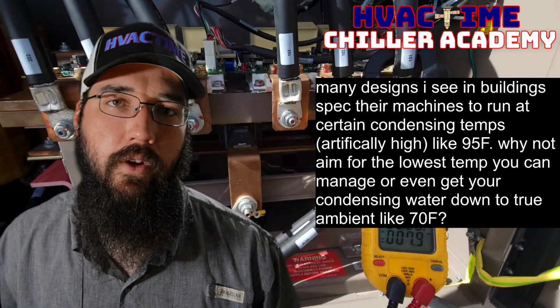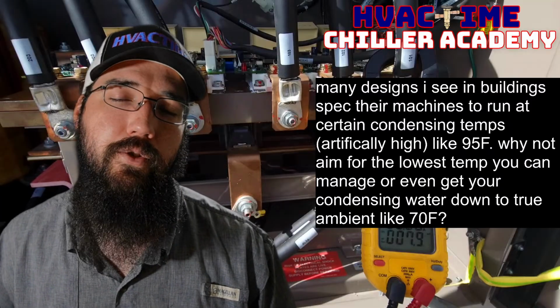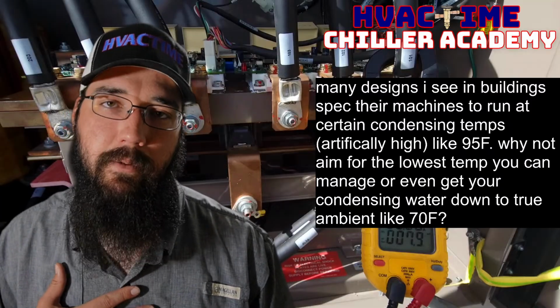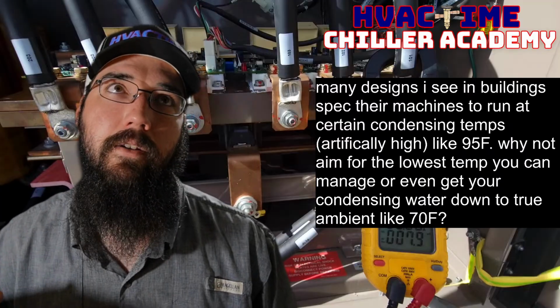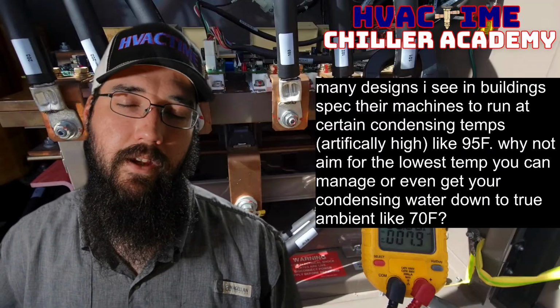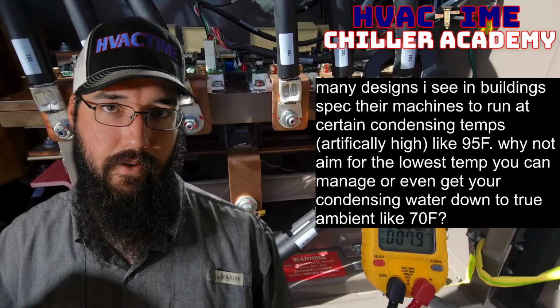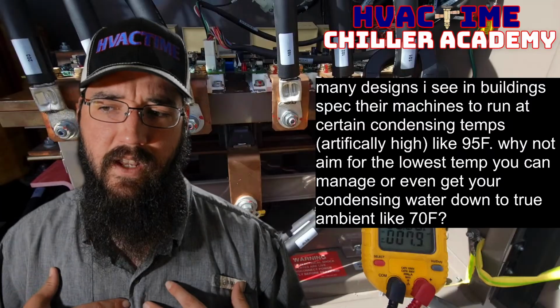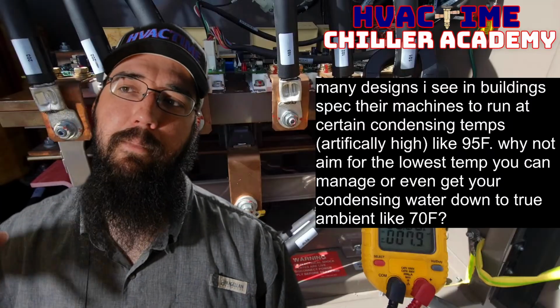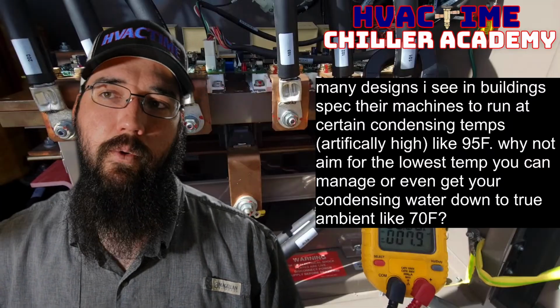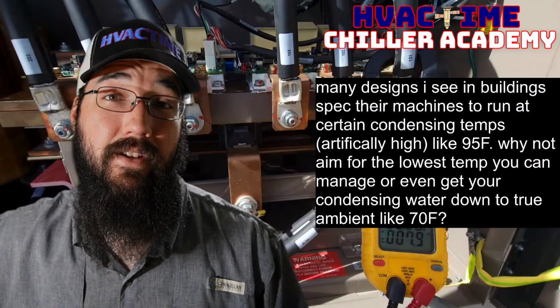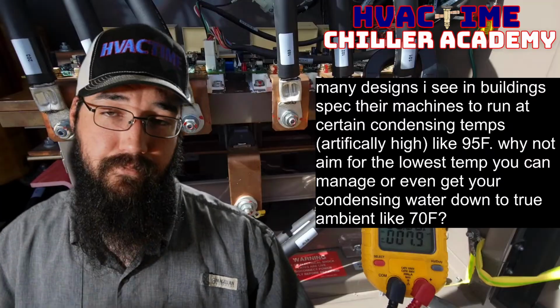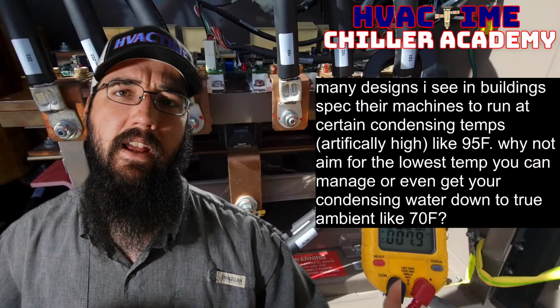So usually with those, 70 degrees is about as low as you can safely operate. And I personally may set a minimum, or the lowest it can go to, about 75 on a machine like that. I personally like to play it a little safe, but I'll set the maximum that one can go to like 85, maybe even 90, depending on the circumstances. Okay, depending on the plant.